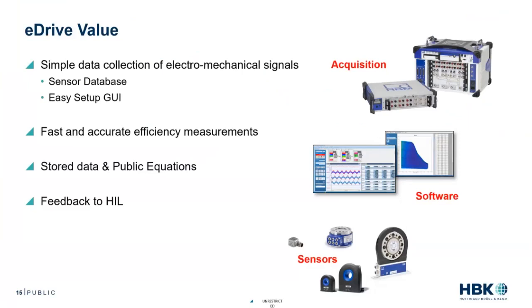At HBK we have a product called eDrive, our motor analysis tool. It's particularly well suited to operate in a power hardware in the loop setting. First, we provide a simple collection of electromechanical signals. In hardware in the loop, that means we can take a wide variety of signals — scaled analog voltages from a simulator, actual current sensors, actual torque sensors, or any sensor you desire. We're flexible enough to bring in a variety of signals so we can look at simulated and real values within the same acquisition system.